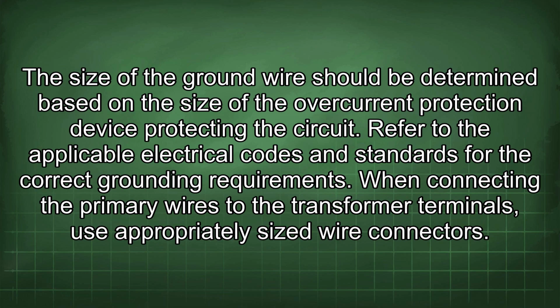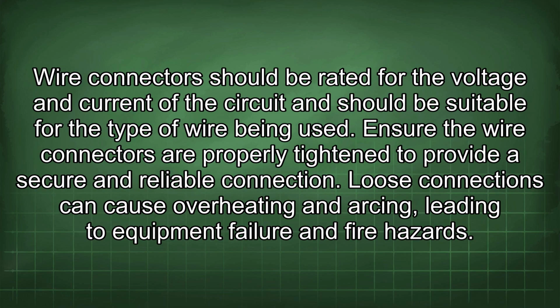When connecting the primary wires to the transformer terminals, use appropriately sized wire connectors. Wire connectors should be rated for the voltage and current of the circuit and should be suitable for the type of wire being used. Ensure the wire connectors are properly tightened to provide a secure and reliable connection. Loose connections can cause overheating and arcing, leading to equipment failure and fire hazards.